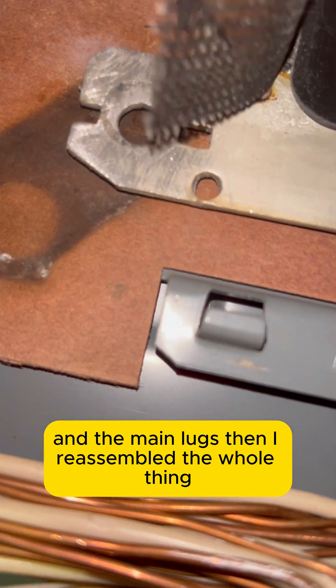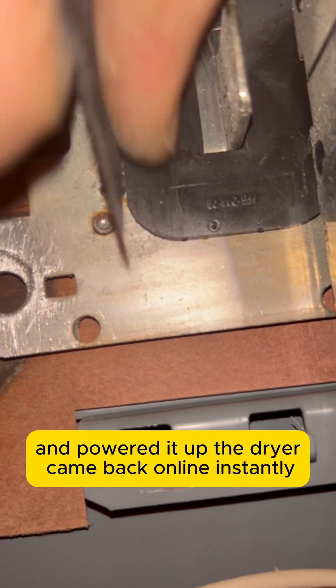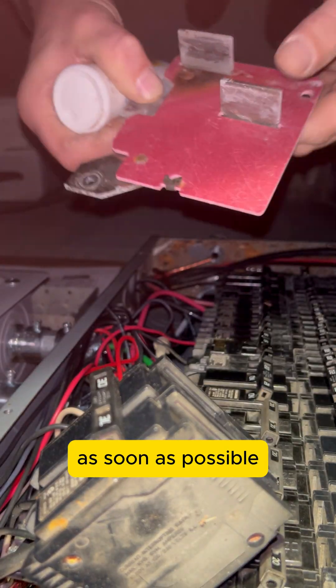Then I reassembled the whole thing, torqued everything back to spec, and powered it up. The dryer came back online instantly and the voltage stabilized right where it should be.